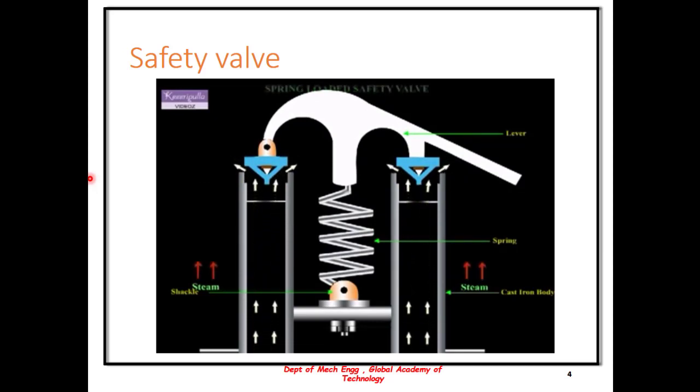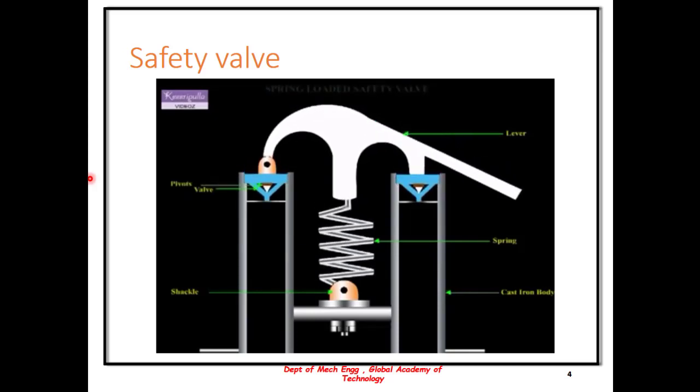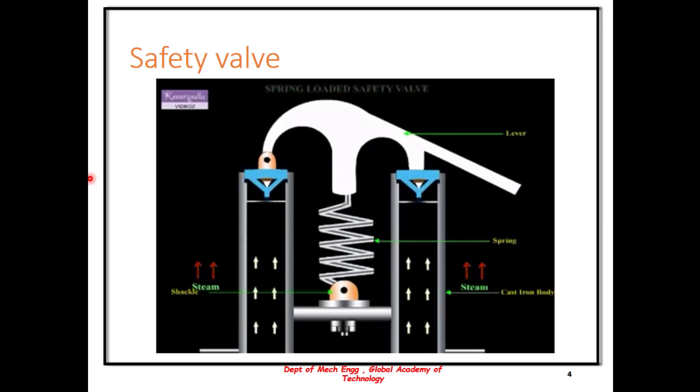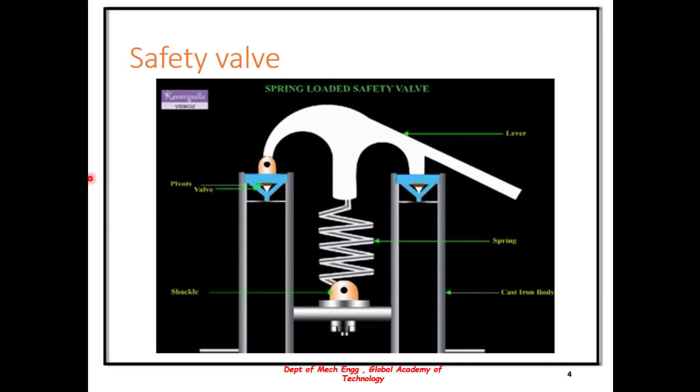The spring loaded safety valve is actuated when the steam pressure exceeds the safe working pressure. The valves rise up against the action of the spring due to the excess pressure of the steam inside the boiler and allow the steam to escape until the pressure drops to the safe working pressure. The spring loaded safety valve is much lighter and compact when compared to other safety valves, so it is preferred for locomotive and marine applications.